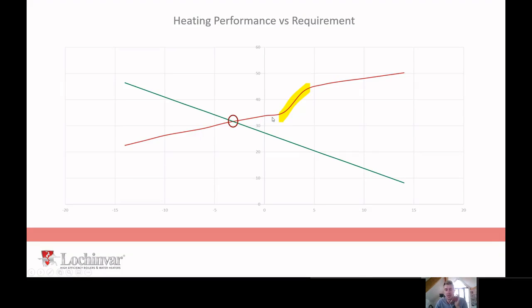When we get beyond 2 degrees, yeah, it's cold outside, but there's just not that much humidity. So any ice that forms on your evaporator is going to be a very fine layer. It's not going to mess up your airflow. The heat pump's going to continue to function effectively. So if you have a heat pump that's going to spend most of its life between 4 and 2 degrees centigrade, it's not going to have a very good time.